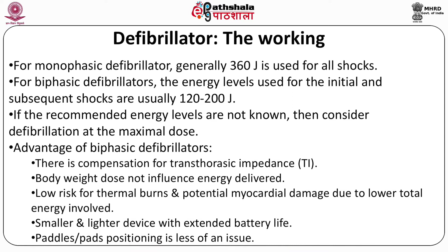There is compensation for transthoracic impedance, or TI. Body weight does not influence energy delivered. Low risk for thermal burns and potential myocardial damage due to lower total energy involved. Smaller and lighter device with extended battery life. Paddles or pads positioning is less of an issue.